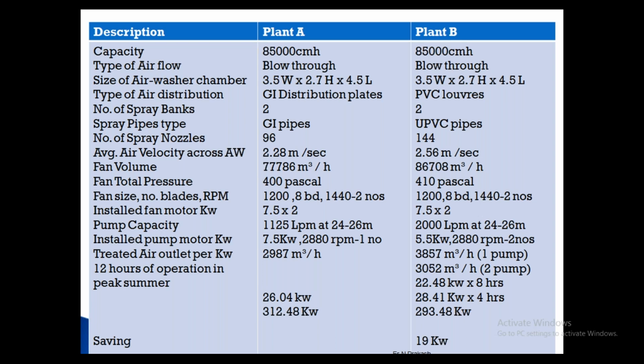Based on this, a calculation which is normally not done: the treated air after the air washer, what we get per hour per kilowatt. We calculated that almost 3000 meter cube per hour per kilowatt was being delivered earlier. After we changed to the two pump system with slightly higher kilowatt, the air delivered per kilowatt was more: for the single pump it was 3857 meter cube per hour, whereas for two pumps it was 3052.